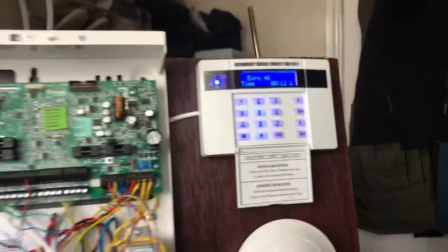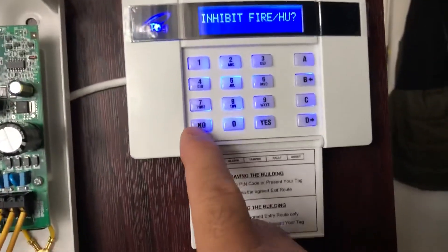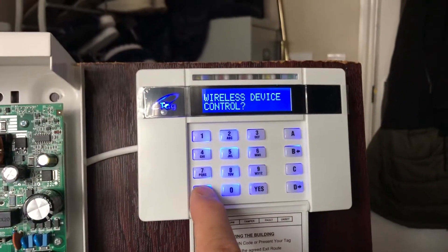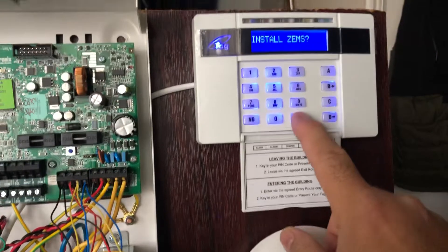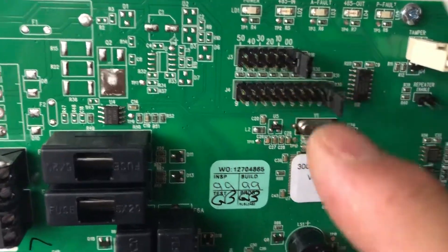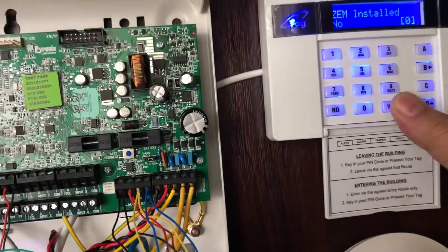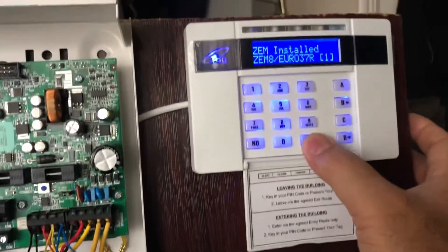So how do you program the expander? Once you've wired up everything and powered on, you need to go to the keypad and go to engineering mode. The engineering code is 1, 1, 1, 1 by default. Then press No, then go to Install ZEM, then press Yes. Address 0 — I'll make this one address 0, as you can see here: 0 and 0. Then press Yes. I need to enable it — press 1. That is enabled. Yes, yes, ok.